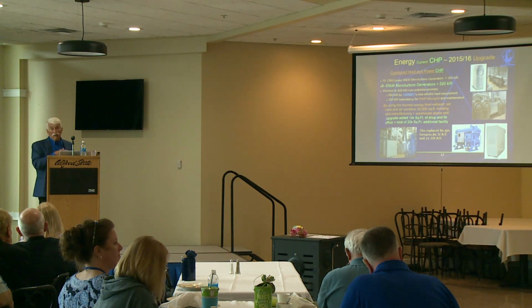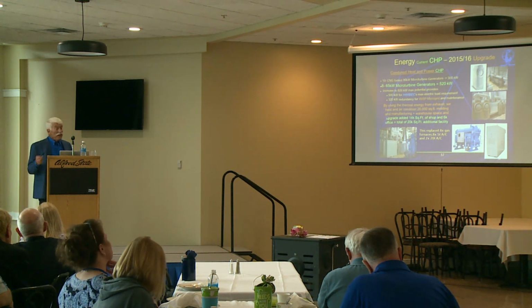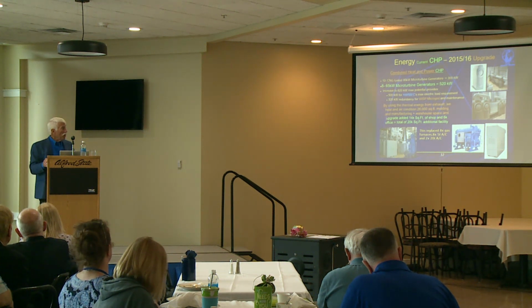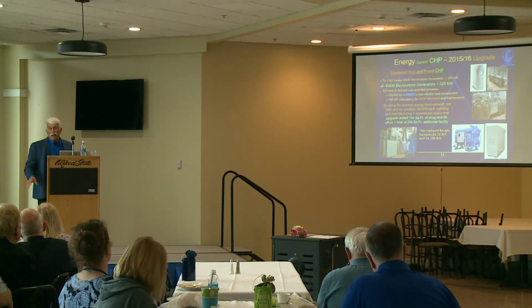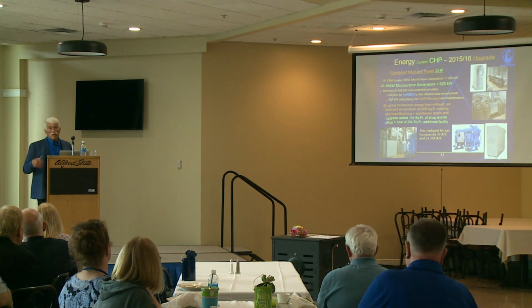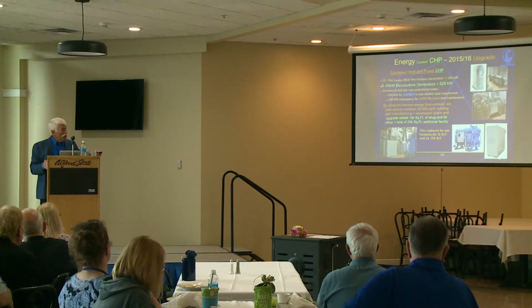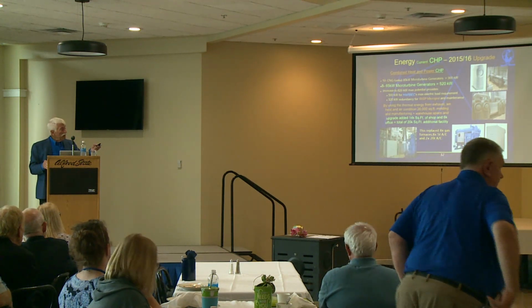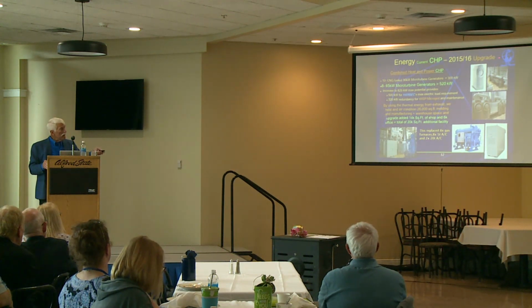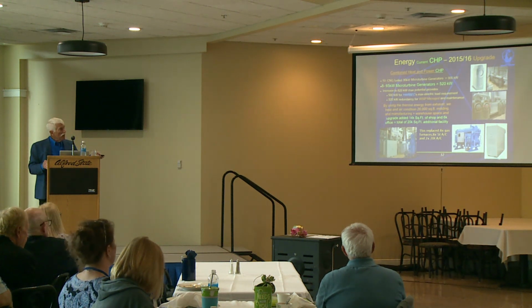We kept part of our old turbines and added 8 new C65 turbines. They were even more efficient, because in the past, how did we get our thermal? We would run the micro turbines and take the exhaust gas to a heat exchanger and create a constant supply of hot water. In the new versions, you can see up on top there, that's an absorption chiller, and these are the original micro turbines, and that's the heat exchanger.